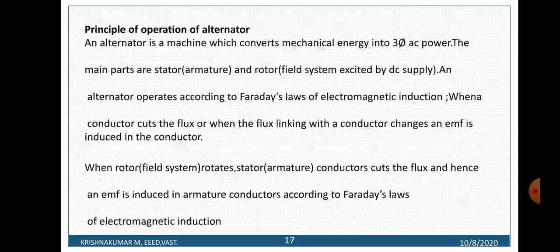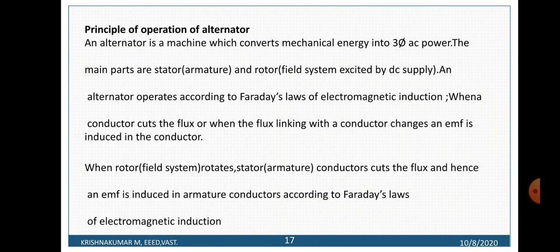Principle of operation of an alternator: An alternator is a machine which converts mechanical energy into electrical energy. The main parts are stator and rotor. The stator consists of armature winding and the rotor consists of field winding, which should be excited by a DC supply. An alternator operates according to Faraday's law of electromagnetic induction. When the field winding is excited from a DC supply, it creates flux. That flux passes through the air gap and cuts the armature winding, and an EMF is induced in the armature according to Faraday's first law of electromagnetic induction.